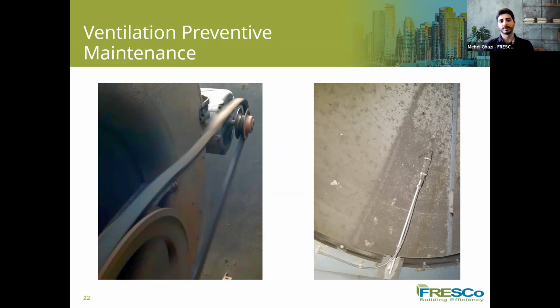Belts are another part that we need to pay attention to. There are several examples of belts that are very loose or broken, and no one is aware that they're broken and not working. When they break, the connection between the motor and the pulley is lost, so the fan won't be rotating and running. The left side photo is an example where you can see how loose the belt is. This can be easily recognized by the noise that we can hear from our makeup air unit. So if we check the makeup air unit just by walking around it quite regularly, this can be recognized.